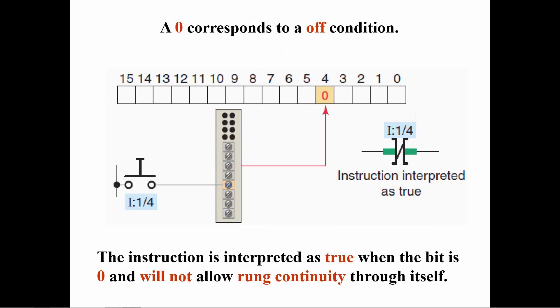If the external switch is not closed, a 0 is placed at the specified address in the input table, and the examine if open instruction becomes true and there is rung continuity through the contact. This is the same as a normally closed contact on a relay whose coil is not energized.